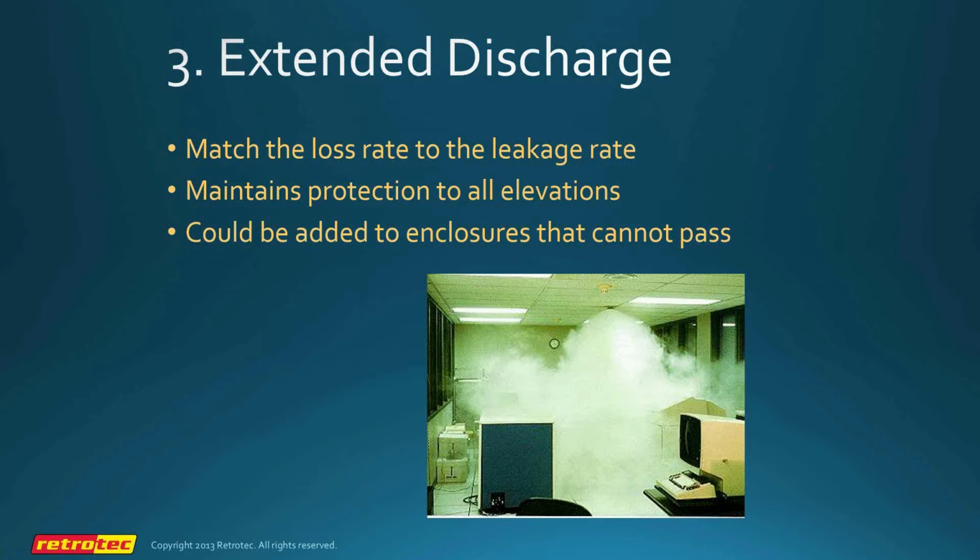The reason why we run into these things is we will often have to make recommendations once the enclosure fails, and adding extended discharge is one of the recommendations that we could make. However, by the time you get to the point of testing the enclosure, it's often too late. And so we say, oh gosh, it's sure too bad that we didn't think about this in the design phase. So that's what I'm attempting with this venting calculator, is to get this figured out in advance.